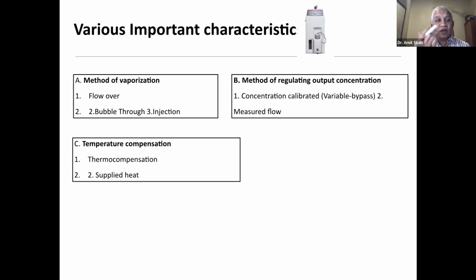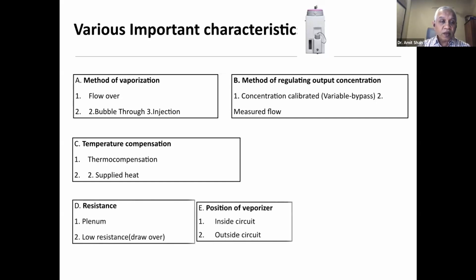Temperature compensation: one is thermo compensation, the second is through supplied heat. The resistance, what do you mean by resistance? Our modern vaporizers are called plenum vaporizers, which have some resistance. So you will require a carrier gas which is slightly higher than atmospheric pressure, which is happening in our circuit. We supply the oxygen at a pressure slightly above atmospheric pressure when it passes through the vaporizer. So that's a plenum vaporizer.